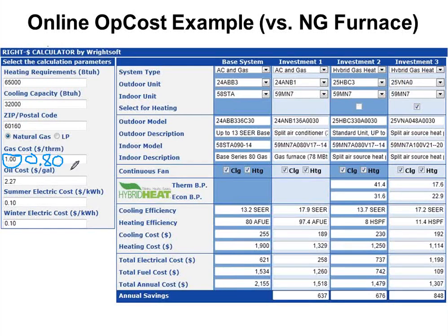When you're doing any analysis for customers, don't look at how much they pay for gas or kilowatt hours. Take the whole bill, the whole dollar amount, and divide it by the total consumption, and then you'll get the total dollars per therm and the total dollars per kilowatt hour. Because if you just look at your gas cost, you may be paying like 40-some cents a therm, but once you put in the fees and distribution charges and taxes, it comes out to more like 70, 80 cents right now. And the electric side is a similar thing.